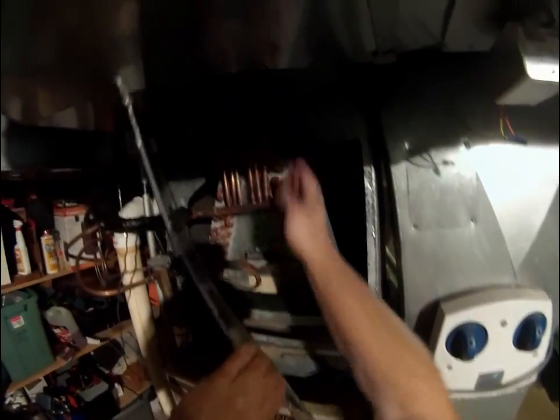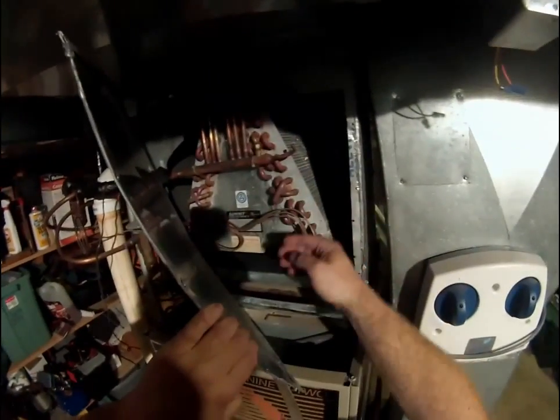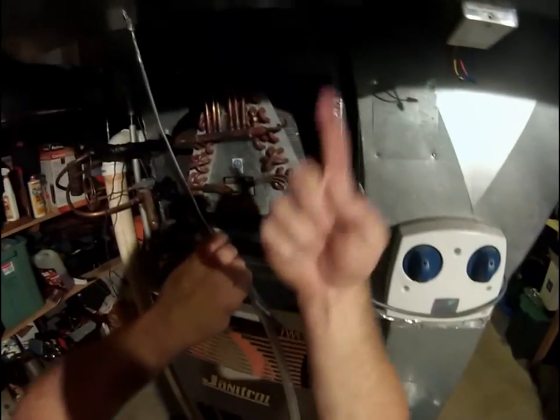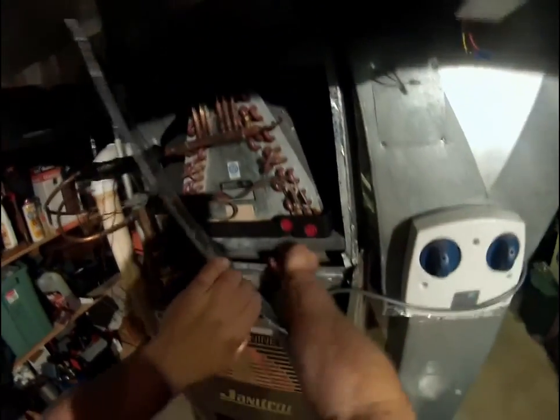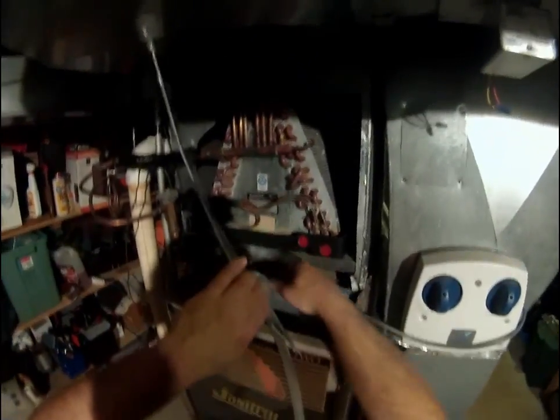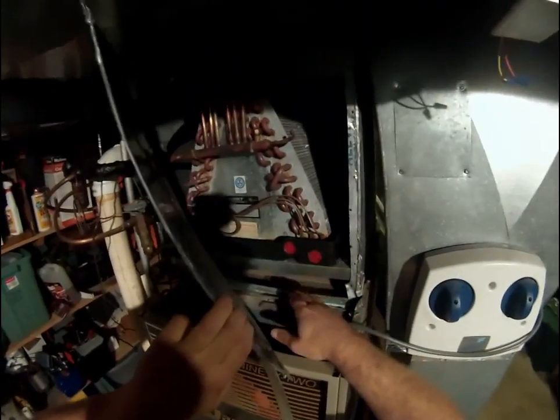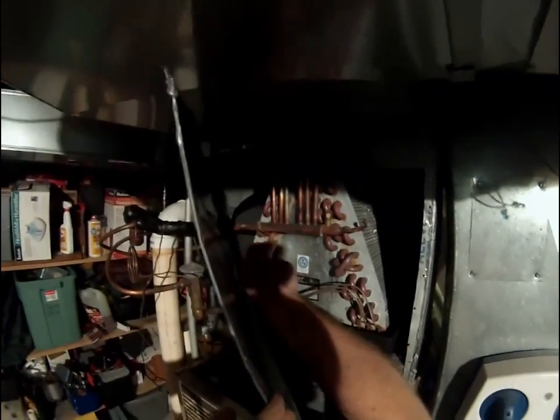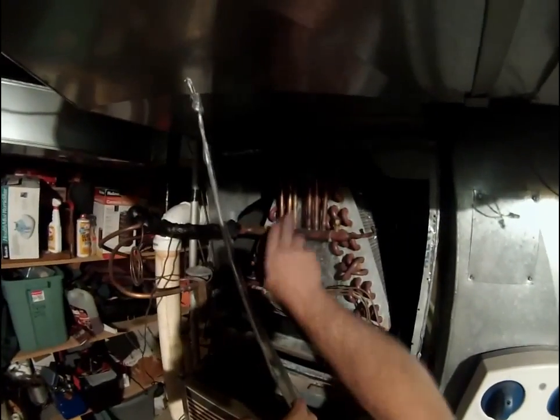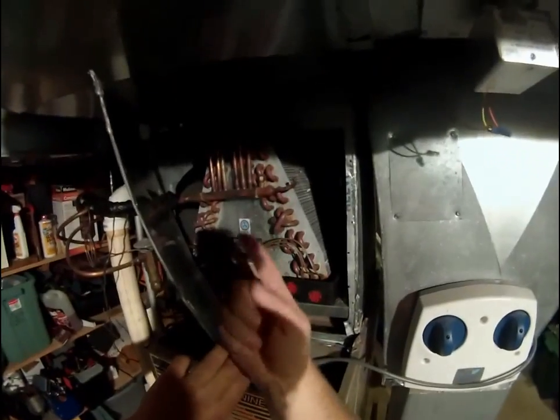Sometimes they'll just be horizontal. Sometimes they're what's called an A-coil this way. And the airflow comes from the bottom up. So most of your dirt is going to pile up underneath here that you're going to want to try to get in there. So you can take out these screws, being real careful not to rupture any of these copper lines or you'll lose your Freon.